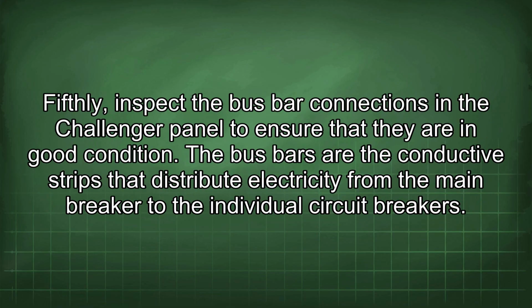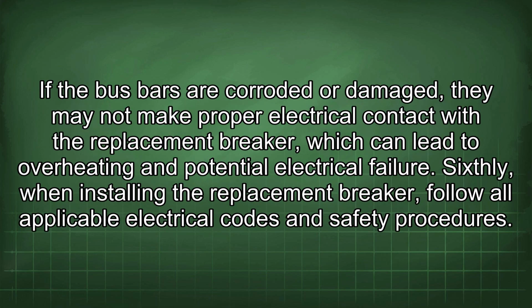Fifthly, inspect the bus bar connections in the Challenger panel to ensure that they are in good condition. The bus bars are the conductive strips that distribute electricity from the main breaker to the individual circuit breakers. If the bus bars are corroded or damaged, they may not make proper electrical contact with the replacement breaker, which can lead to overheating and potential electrical failure.